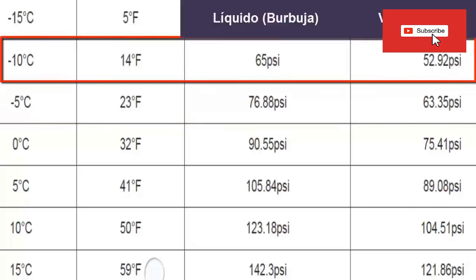For example, to achieve a temperature at the inlet of the evaporator of minus 10 degrees Celsius, an absolute pressure of 65 psi must be at the low side. On the other hand, if it requires minus 10 degrees at the evaporator outlet, then it must work with an absolute low pressure of 52.92 psi. Remember these table values — subtracting your local atmospheric pressure; you can use 14.7 psi for a quick calculation.